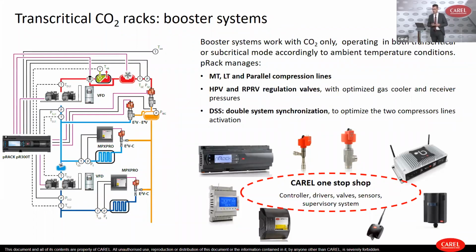Then we come to the transcritical CO2 booster racks. Even here, the pRack controller can support all the needs of the rack. So, of course, the compressor lines, and in this case, even the parallel compressor lines, the lines that we use in case of high temperature and high mass flow of flash gas coming from the receiver in high temperature conditions. At the same time, this controller is able to manage the transcritical valves, high pressure and flash gas valve, some heat recovery systems, and some more features, for example, the water chiller function, or other special features that you would like to manage with this controller. These are our standard CO2 solutions, let's say.